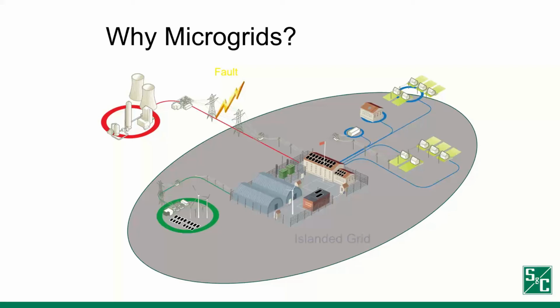In this example, we are showing a use case where there's a fault in the distribution system, and the microgrid protection would detect that, and the control manages the local DERs within the boundary of the microgrid, such that the microgrid would disconnect from the grid and form an island. When the fault is cleared, the control system would again communicate with the DERs and adjust their power outputs such that the system can securely connect back to the grid.